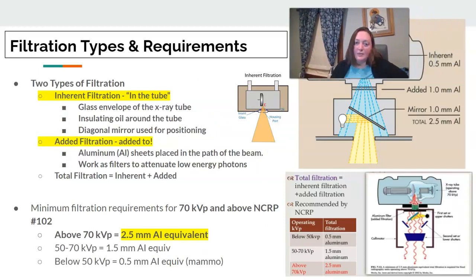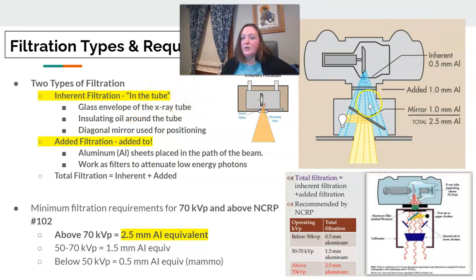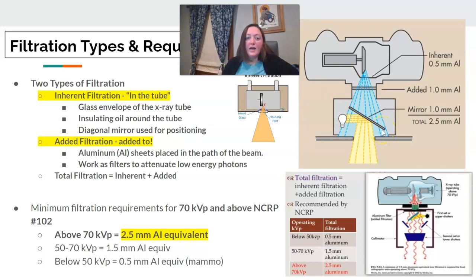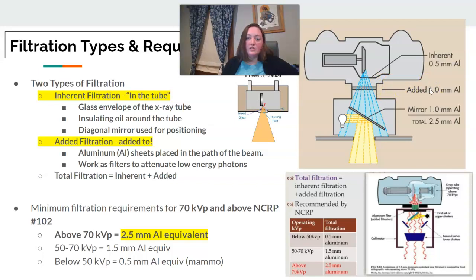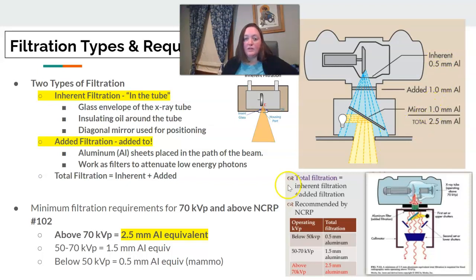There are two types of filtration. Inherent filtration is built into your tube — this involves the glass envelope, the insulating oil, and a diagonal mirror used for positioning. Added filtration is filtration added to the tube, usually aluminum sheets placed into the path of the beam to attenuate the low-energy photons. Calculated together, for equipment working over 70 KVP, according to NCRP 102, we should have a minimum of 2.5 millimeters of aluminum equivalent.